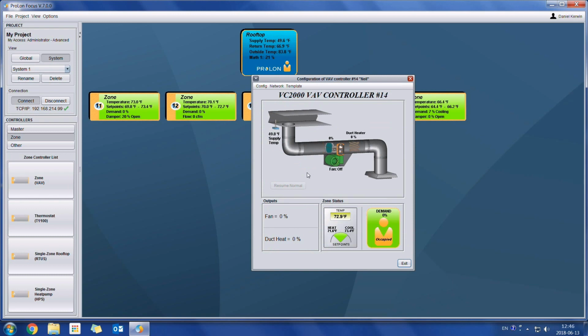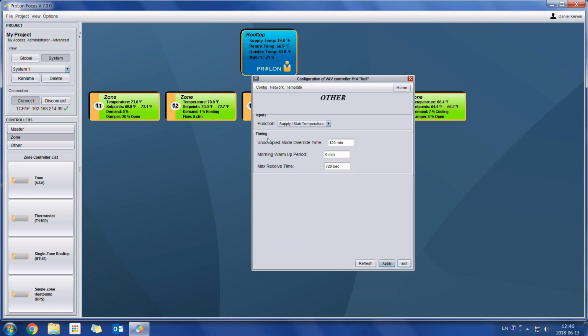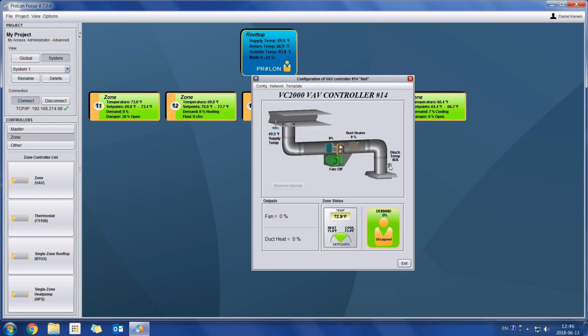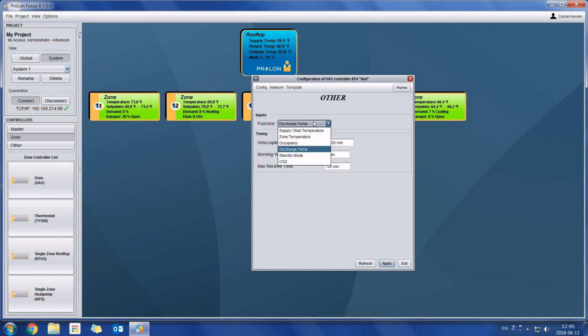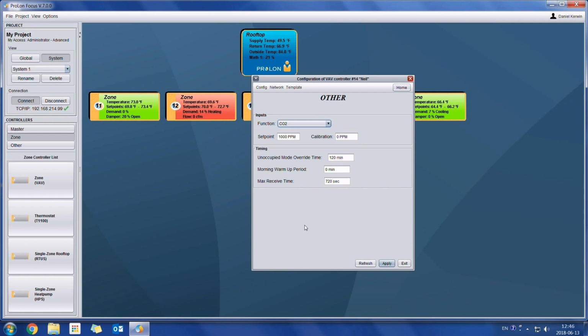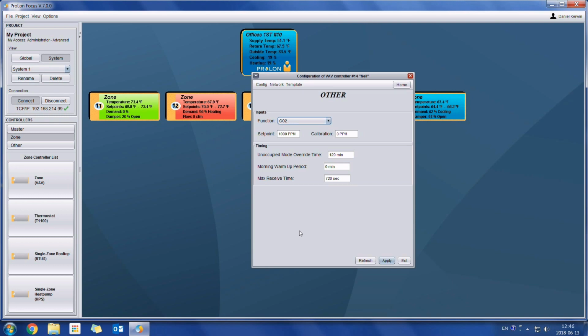The VAV controller has an analog input which can be used for different purposes. So I could go on config other right here, and here we can choose what that input is going to do. One thing we could look at is the discharge temperature. In this case we would be monitoring the discharge temperature after our duct heater. We can use that input for other functions as well. We can use it to monitor CO2 levels, so now we'll know how much CO2 is in the space.